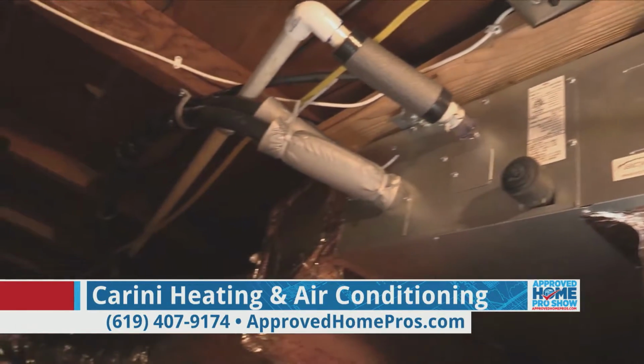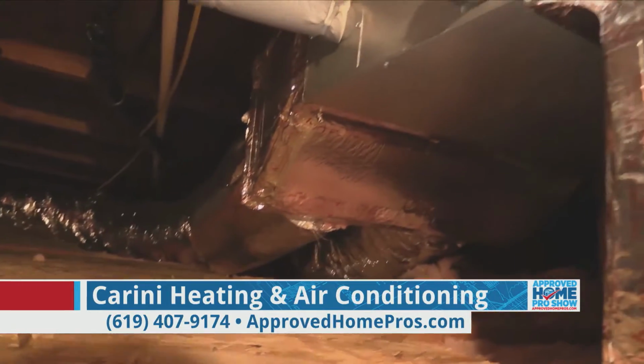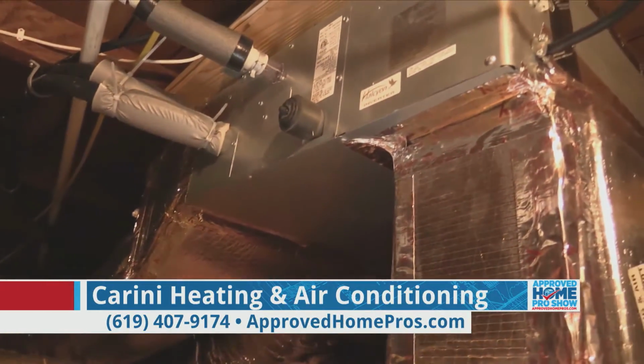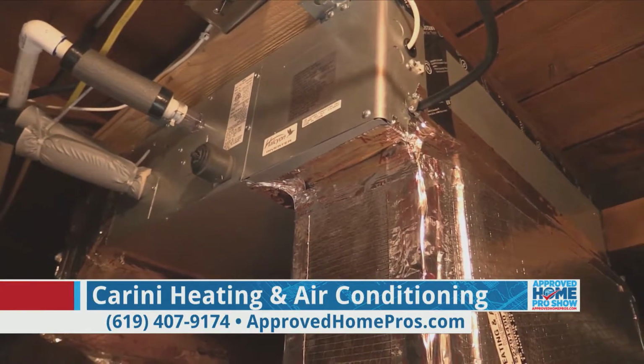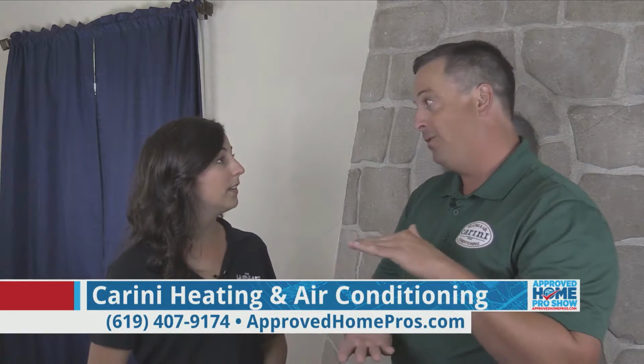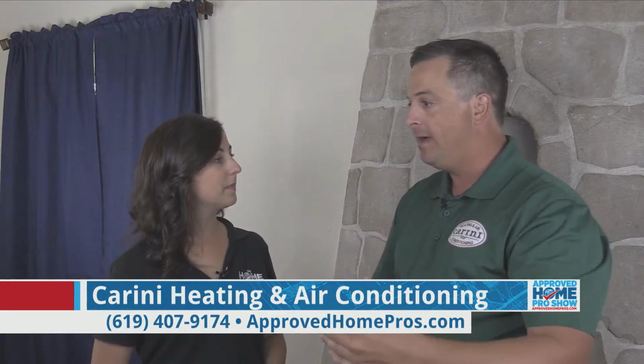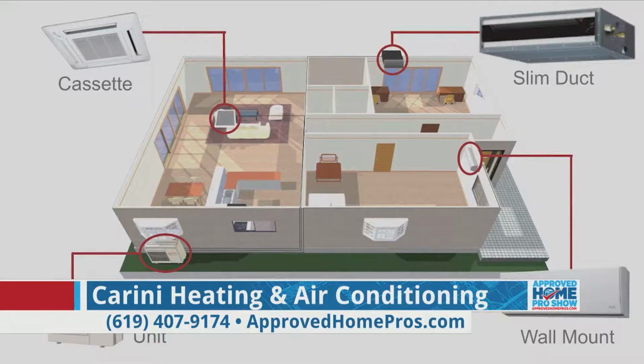So why would someone choose this method of cooling over, say, a traditional HVAC system? Well, this house is a perfect example of the benefits of using this type of system, because in this home, they had very minimal space underneath. In the crawl space, the attic space was very, very small, so you couldn't fit a furnace or a conventional air conditioning system in this house. So with this style of system, they're only 7 inches tall. Oh, wow. So we only need about 24 inches of height to be able to install one of these systems. So in this house, we zoned it, so there's separate areas, different air handlers, and control over separate parts of the house. So this house specifically was a perfect example of why these systems are beneficial.